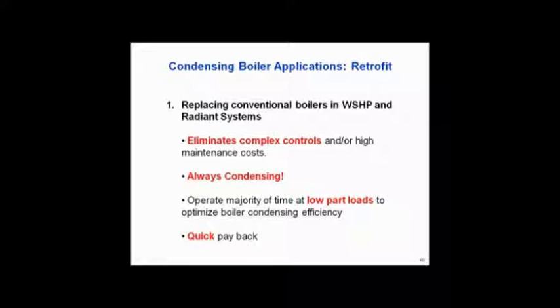I really believe that strongly because another thing we didn't mention to you — these old non-condensing boilers have very complex controls on them. I can do away with all that stuff, get rid of the three-way valves and the blending valves. Just put condensing boilers in there — I don't care how cold the water is. You eliminate a bunch of controls and a bunch of maintenance costs. That water source heat pump loop is always condensing, always at part load, and most important to you on a retrofit: quick payback.